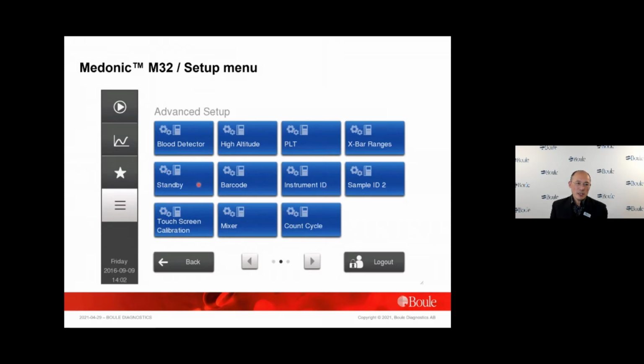And here with the advanced setup, for the blood detector, which is located inside the shear valve, we can set a time to bypass the blood detector to aspirate the whole blood. So if the end user needs to run a special body fluid which has low conductance, which the blood sensor cannot sense, then the end user can set a fixed time for aspirating the sample inside the shear valve channel. But the exact time depends on the viscosity of the fluid and needs to be checked by trial and error to get a correct transfer time.